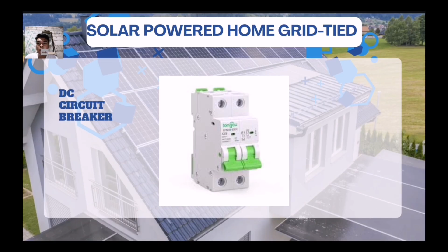So, parts din ng solar powered home grid-tied is DC circuit breaker. DC circuit breaker, ano nga ba ito? Ano nga ba ang ginagawa ng DC circuit breaker at bakit kailangan ito sa solar powered home grid-tied? The circuit breaker is sometimes referred to as the PV disconnect, placed between the solar panels and the inverter, or in some cases, built into the inverter. So, ang DC circuit breaker daw ay nilalagay sa pagitan ng solar panels and inverter. Built into the inverter. So, just like a typical circuit breaker, it acts as an overcurrent protective device.